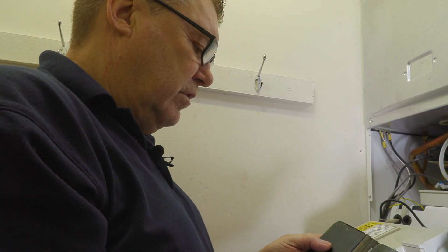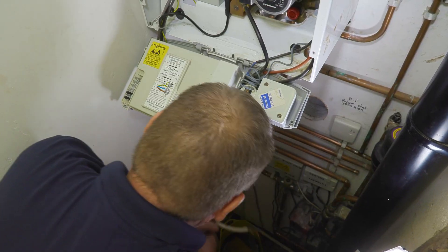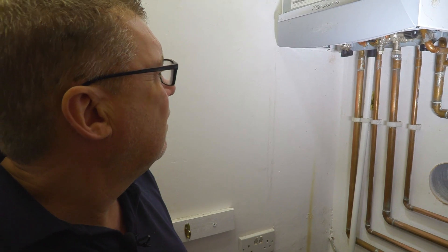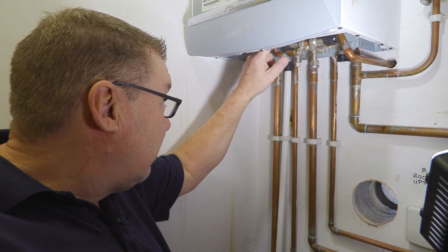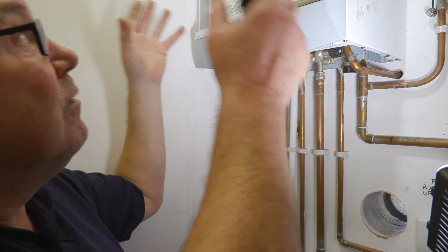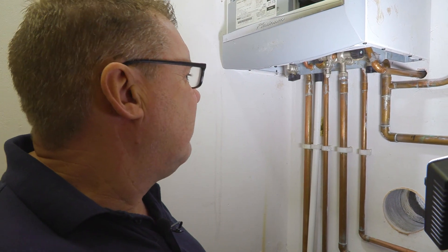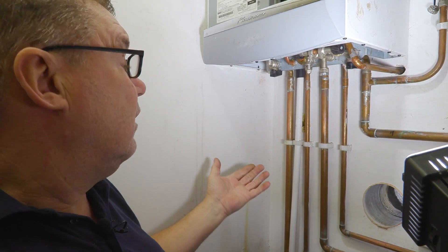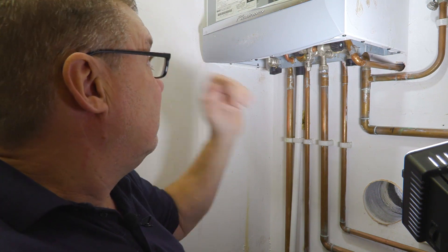As it's a straight change I'm just going to take a quick picture of the electrical box because it's going to go back exactly the way it came out. So we've disconnected the electric supply. Now we can just isolate the flow and return and gas from underneath the boiler and loosen these five connections. The jig remains on the wall and we can lift the boiler off once we remove the flue. In this instance because we're changing the MagnaClean and a few other bits of pipework, we've drained and flushed the system and we're actually replacing the jig too — there's a leaking isolation valve there, and the jig is 10 years old so we might as well replace it.